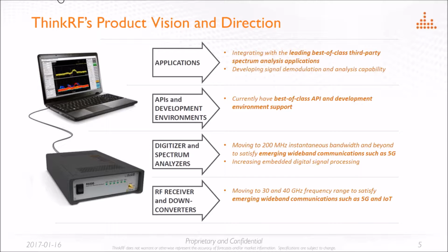That's a market-leading spec when you compare it with benchtop spectrum analyzers. In terms of phase noise, Tim, was that the question? Yeah, sorry, phase noise specifications. In terms of phase noise, our products are very consistent with, for instance, Keysight's X-series analyzers. We've actually done some benchmarking in that area and are happy to provide that to interested parties.